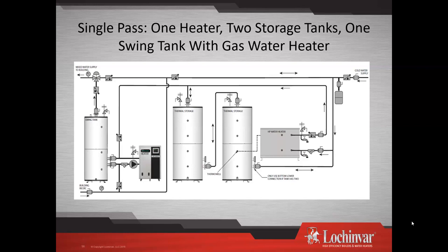So what we've done to try to make it so that some of these projects can even move forward, because the cost is just hard for most building owners to swallow, is we've upsized the storage and downsized the heat pump. In doing that, we can create a significant cost savings. At the same time, I think most would agree that heat pump technology is going to continue to evolve over the next decade, and there's going to be a lot of improvements. So personally, I like the idea of putting more of my investment into a non-moving part that's going to sit there and be reliable.